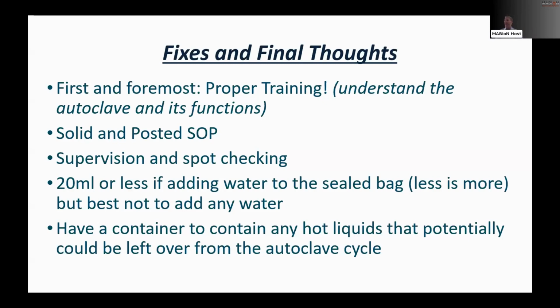Now you don't have to worry about bags being open, closed, anything rupturing on the inside. And with this product, at the end of the cycle, let's say the autoclave failed. They never fail, but just in case one actually does break down, the valves shut back up, you can pull it out. Now you can store it, take it somewhere else into another autoclave. It goes back to being airtight. You stick it in another autoclave, restart, and away you go.